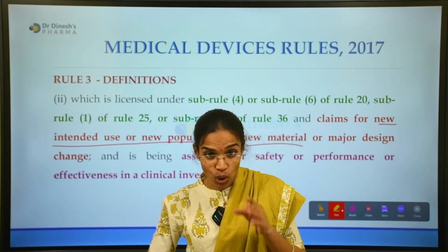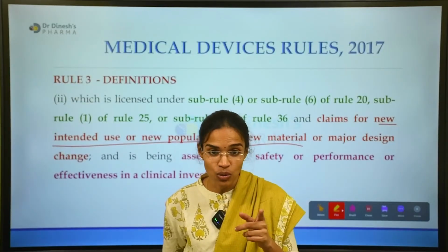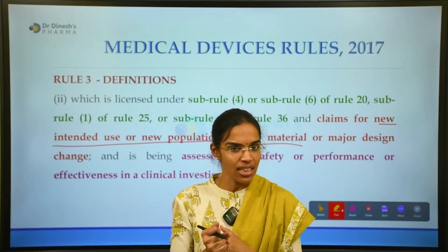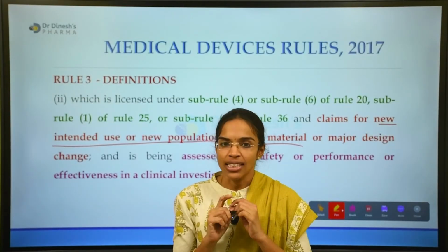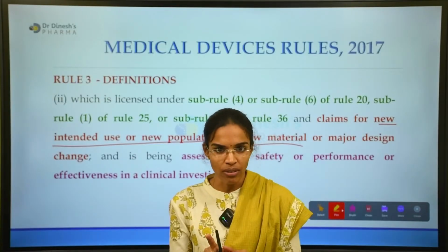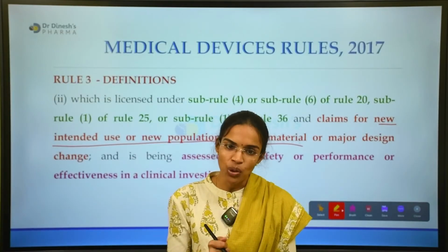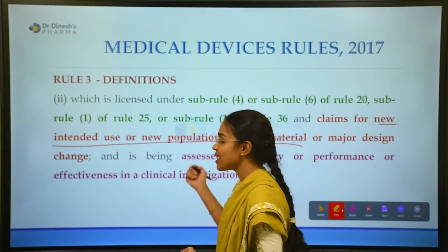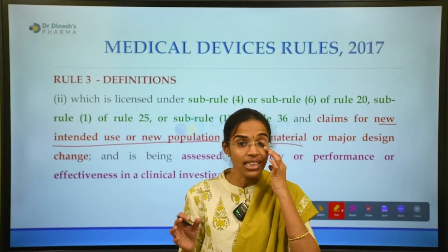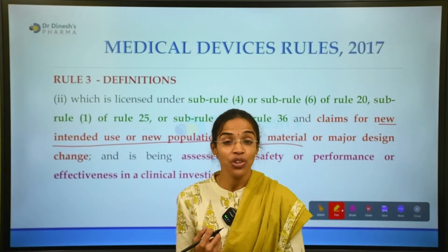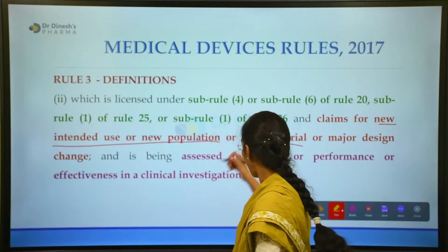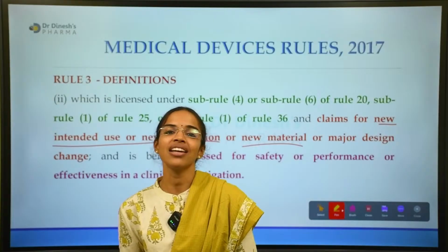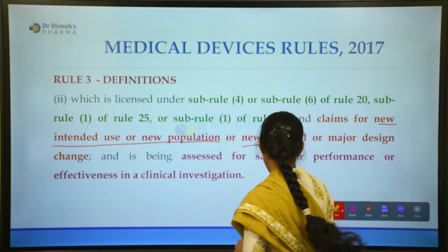investigational medical device, not only new devices. That is the concept here. An investigational medical device does not necessarily mean a new device. It may be a new device, or one which does not have a predicate device, or an already licensed or existing device but with a new intended use, or a new material, or improvised for a new population. That is an investigational medical device.